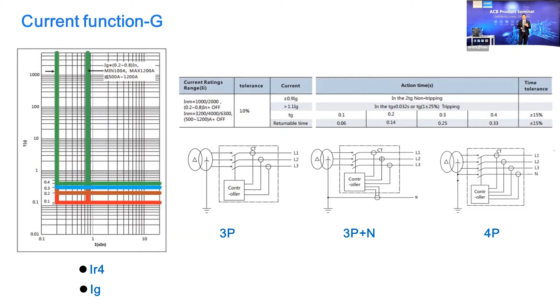But remember, if the breaker is 3-pole, please add the neutral CT. If you need the grounding protection and the breaker is 3-pole, please remember you need to add the neutral CT, like the middle joints, like this one. Put the CT on the neutral phase. But for the 4-pole, no problem, because inside the breaker we have the CT inside. This is the grounding protection.